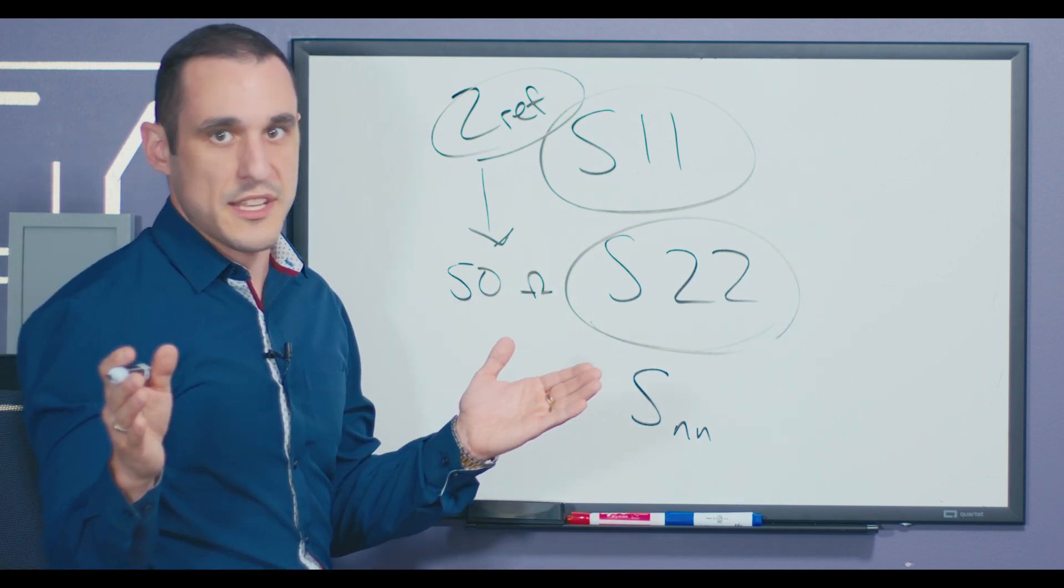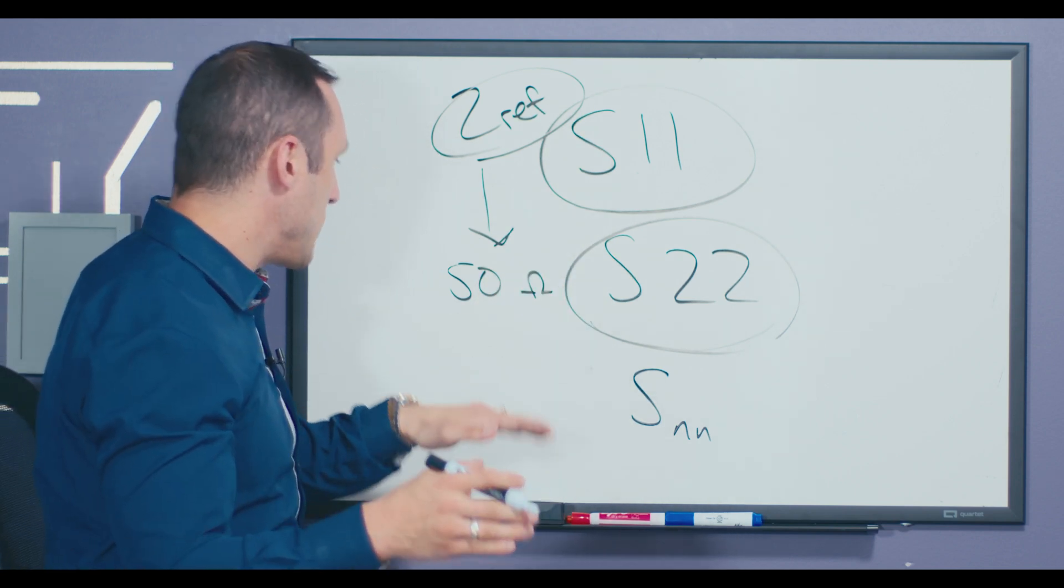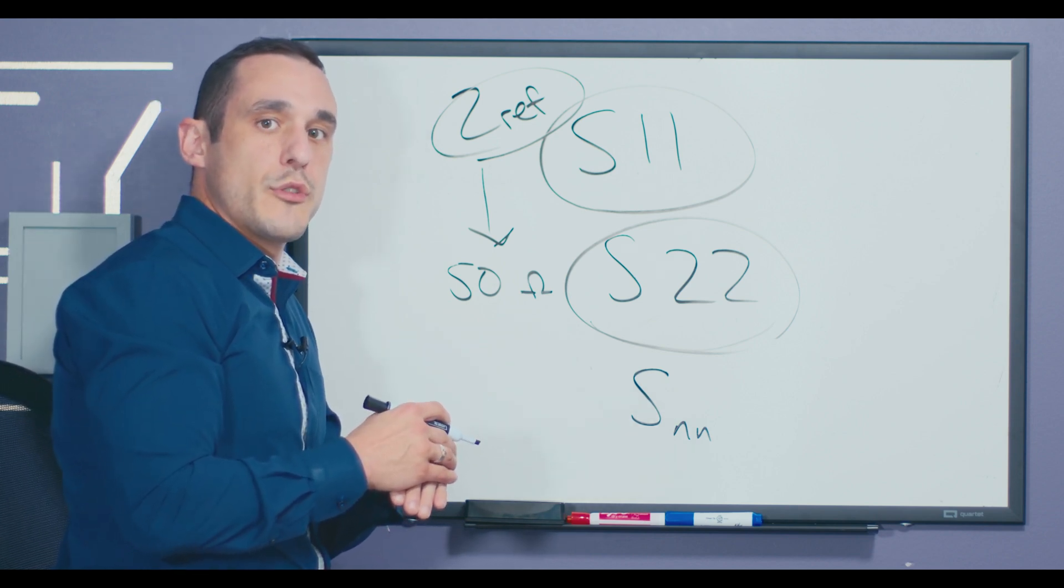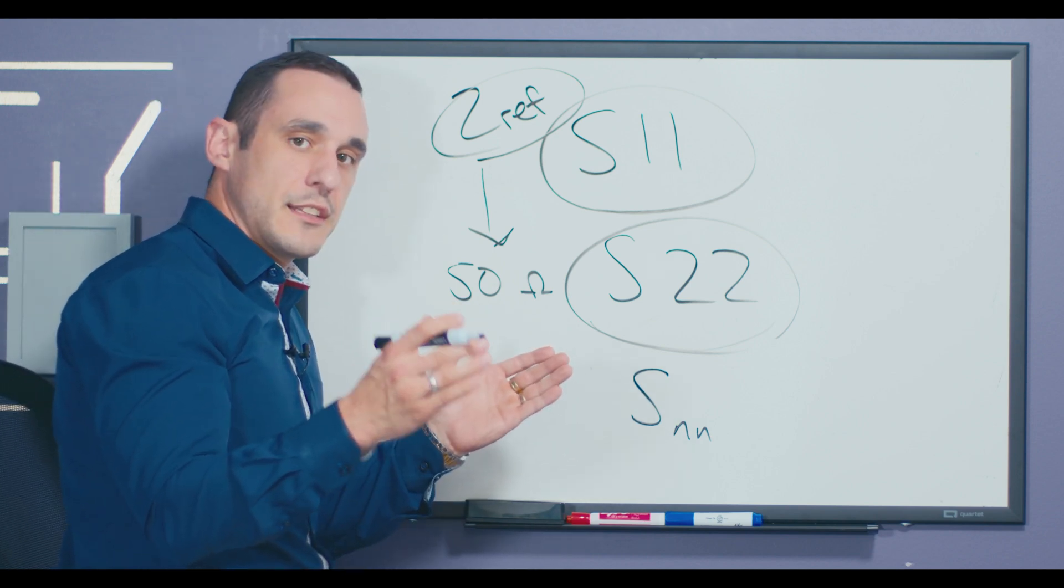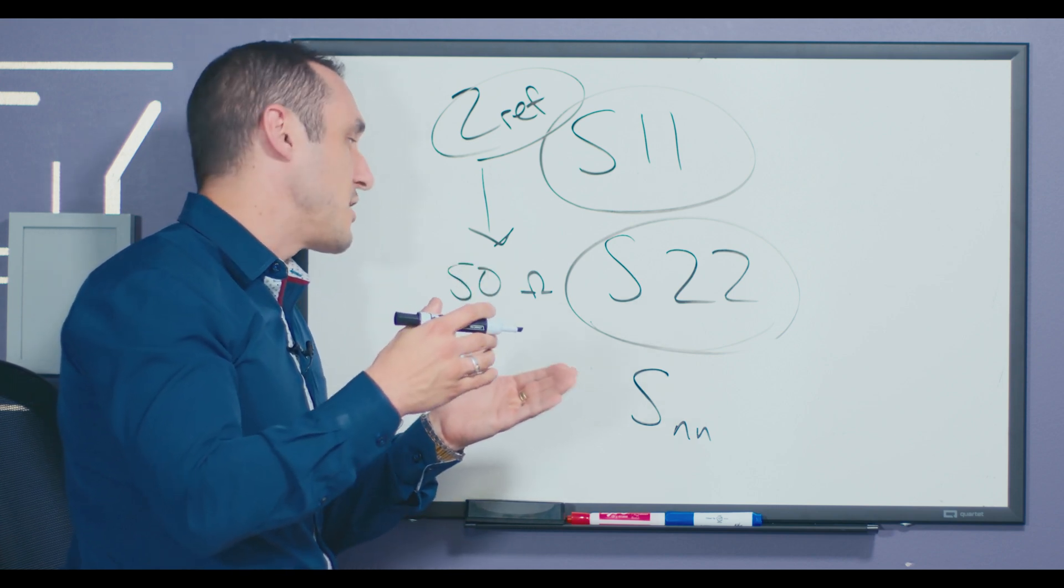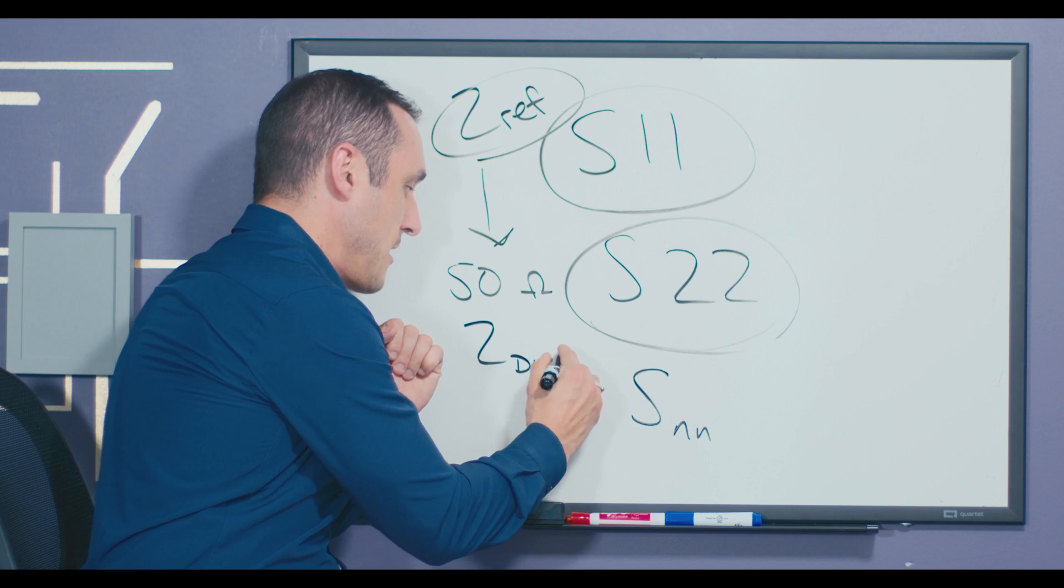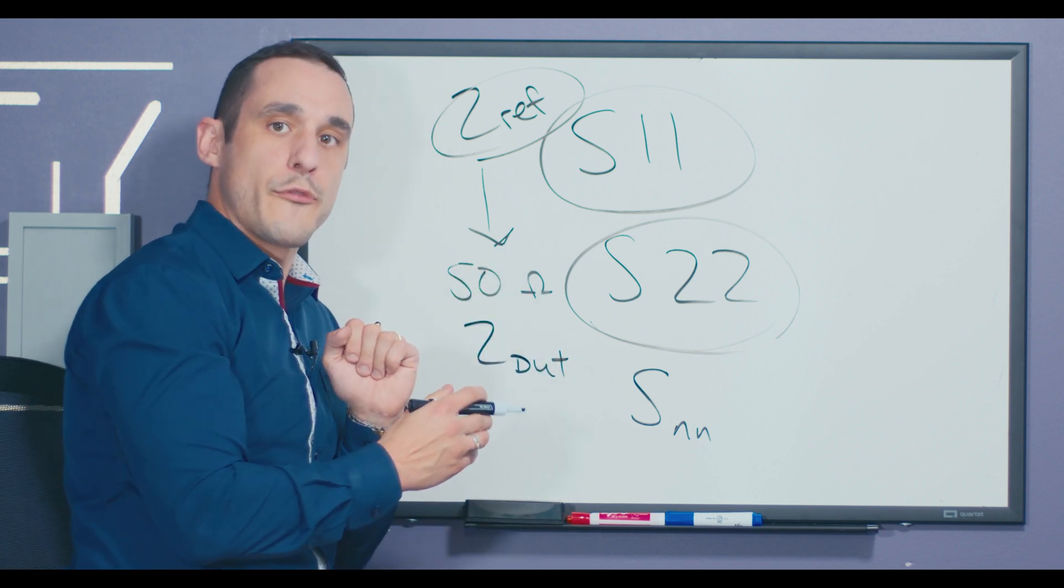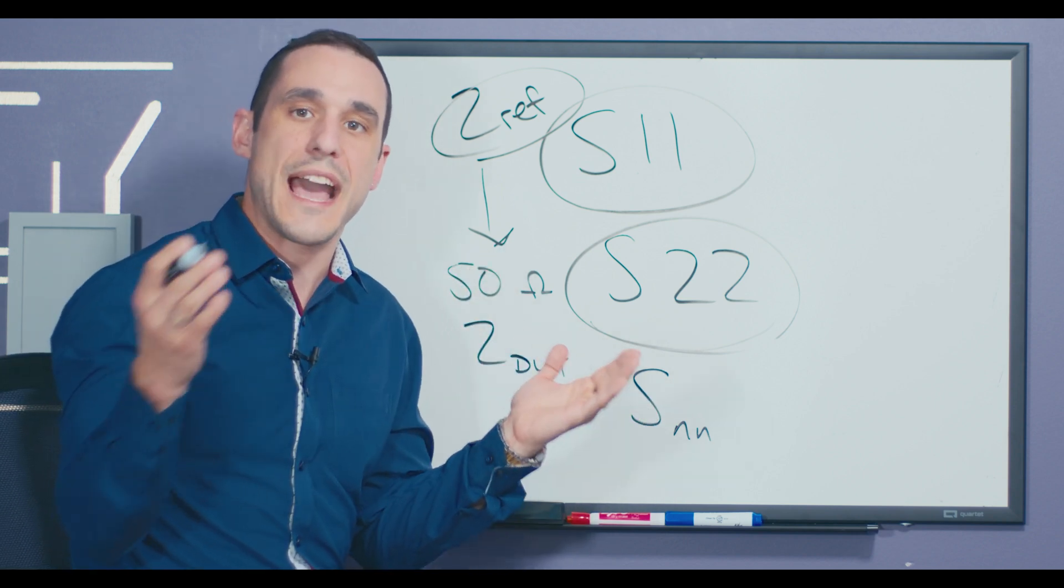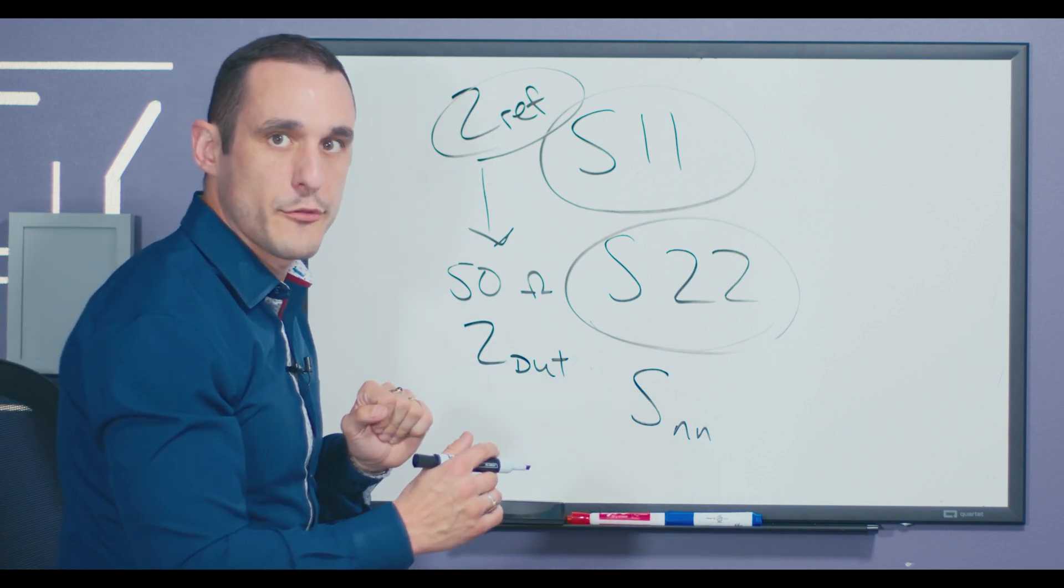Sometimes in a 70 or 75 ohm system it's going to be set differently, but generally it's set to 50 ohms. And so what you're doing is you are comparing the electromagnetic wave energy that is reflected from your impedance of your device under test at the interface with a 50 ohm reference. So in order to do this we have to calibrate our instrument against a 50 ohm reference.